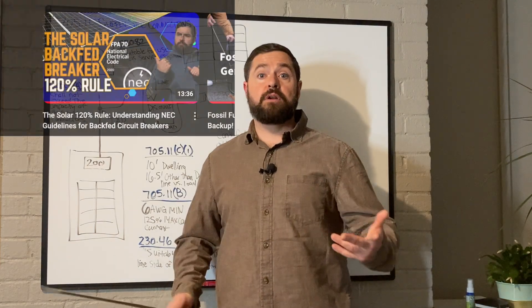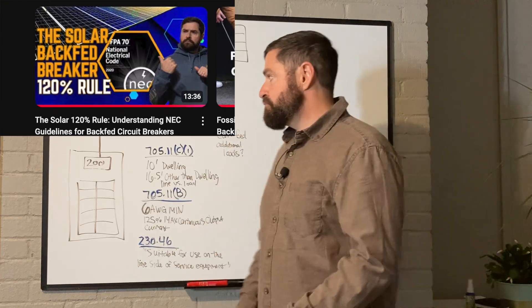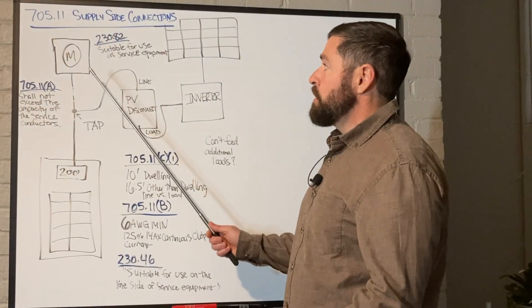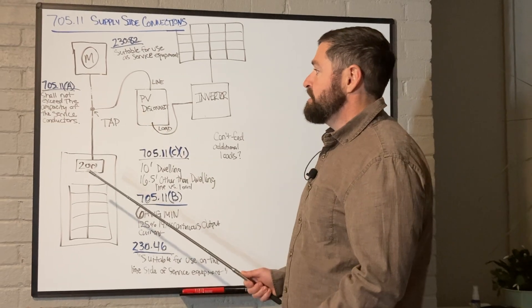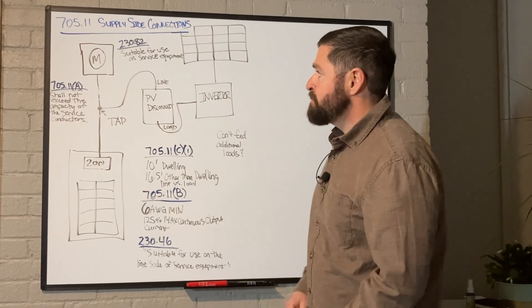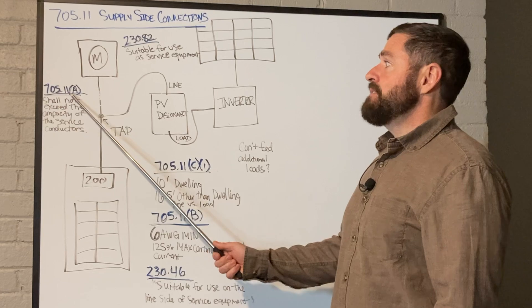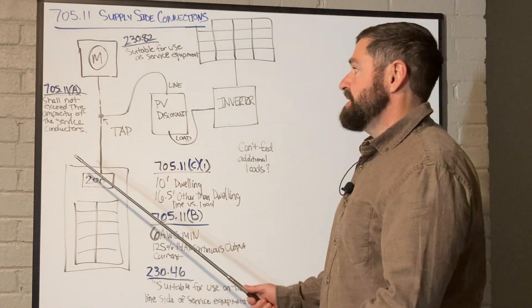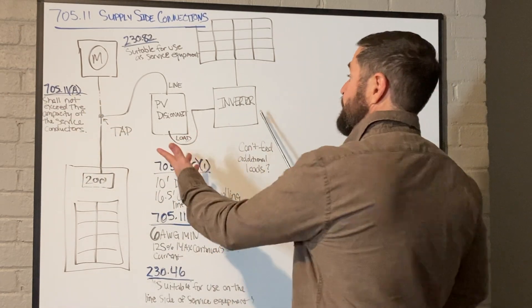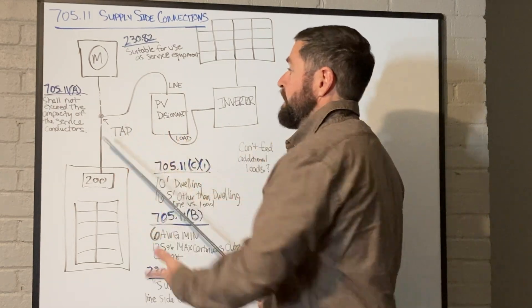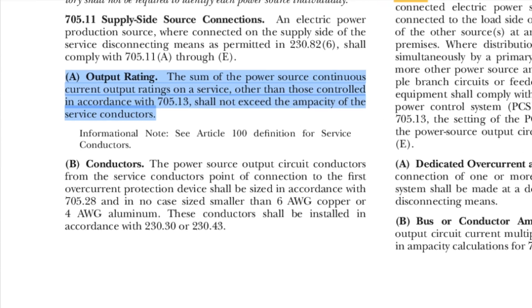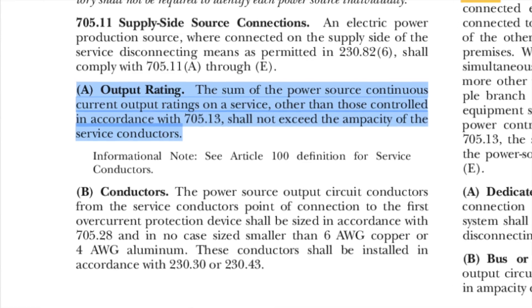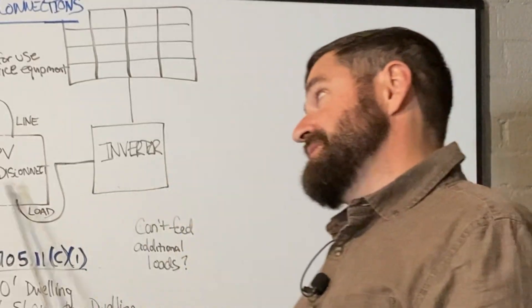Basically, we are going to tap between the utility meter and the service disconnecting means. Right off the bat, 705.11a essentially is saying the PV system that you're connecting cannot exceed the ampacity of the service conductors. So if you have a 200 amp service, then your PV system cannot exceed 200 amps.